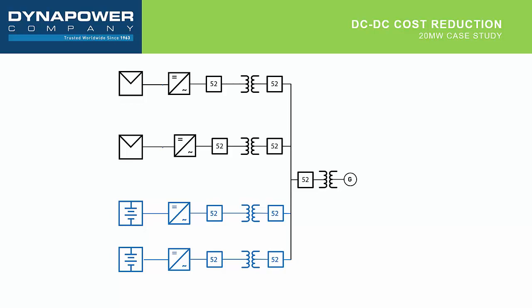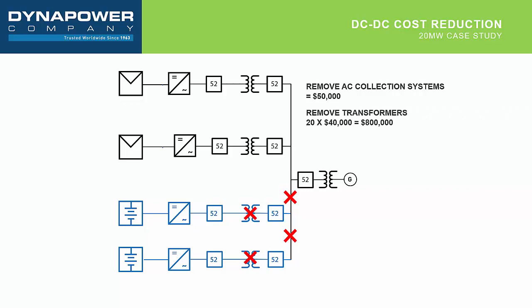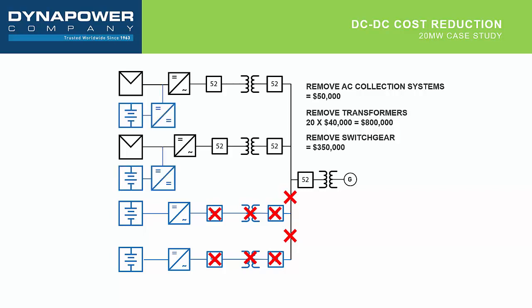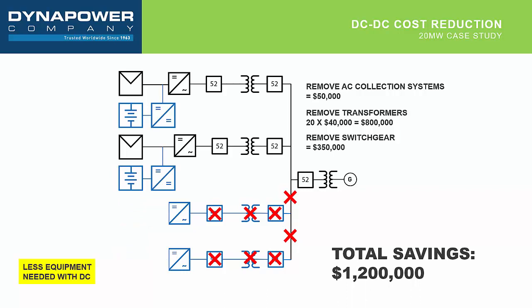Now, as we start to go through this and look at what happens when we shift from AC coupled to DC coupled, we'll see the removal of different major components. First, there's the removal of the AC collection system. Then there's also the removal of all the individual transformers as are typically used in the AC coupled storage configuration. Then, of course, the switchgear as well is removed. Then, of course, we're parking the system on the PV bus behind the PV inverter. The net result of the removal of this equipment needed for the AC coupled system is a theoretical savings of $1.2 million on a typical or standard 20 megawatt array. Substantial figures, and this is why DC coupling is pointed to frequently as a more cost-effective topology.